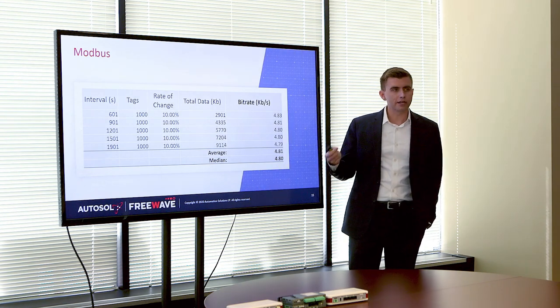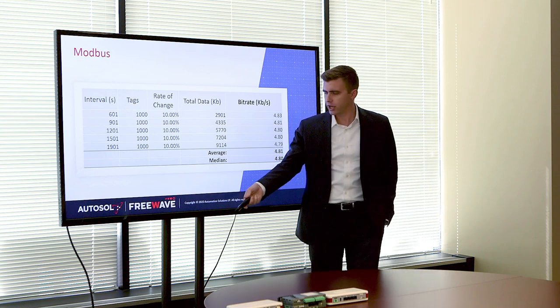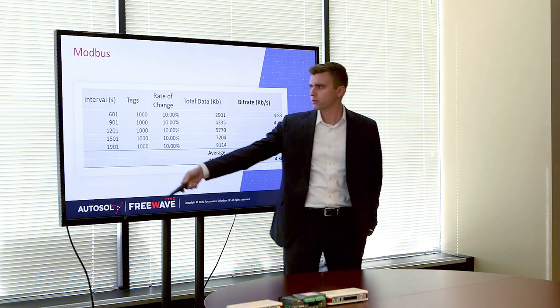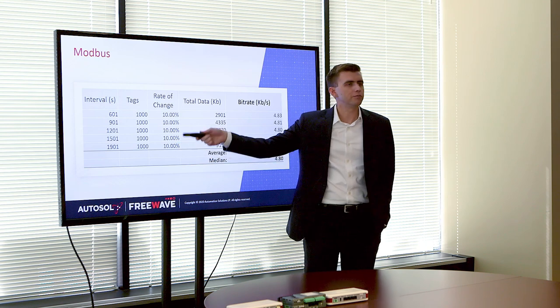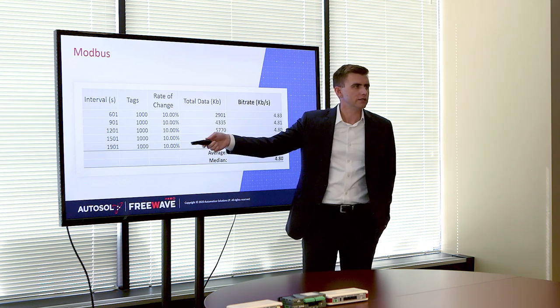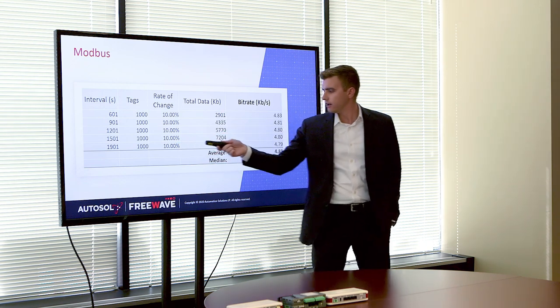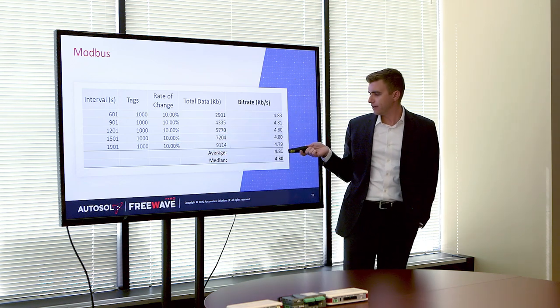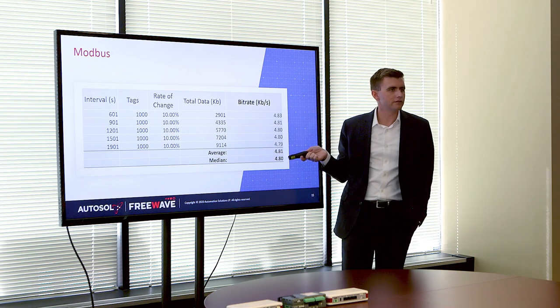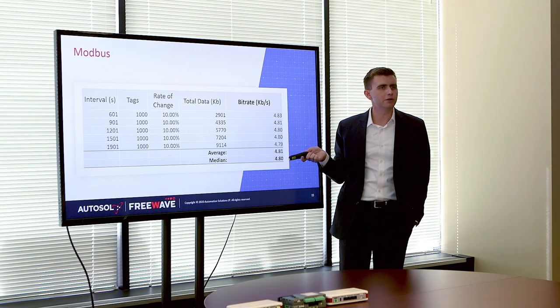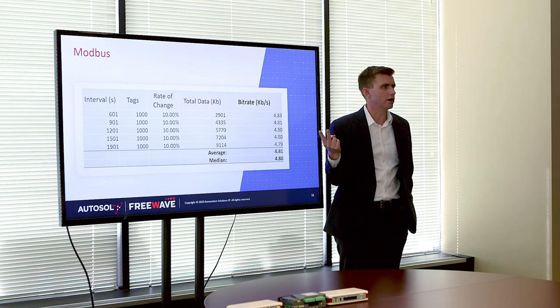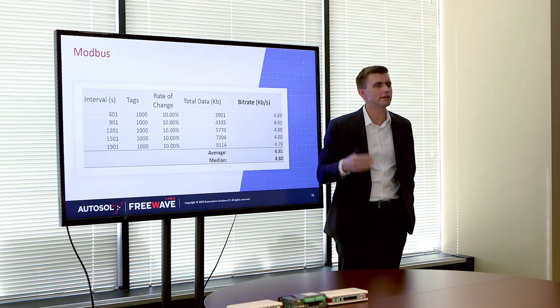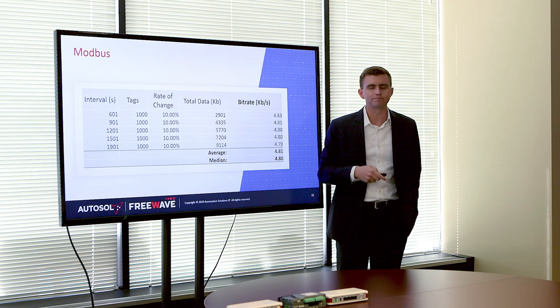In another test with Modbus, we changed the time interval from 10 minutes to 30 minutes, leaving the rate of change at 10% to hammer home the point — again 4.81 and 4.8 kilobits per second. There's not a lot of deviation in how much bandwidth was consumed, no matter how long we polled or what the rate of change was, because in poll-response we send everything that's requested no matter what.